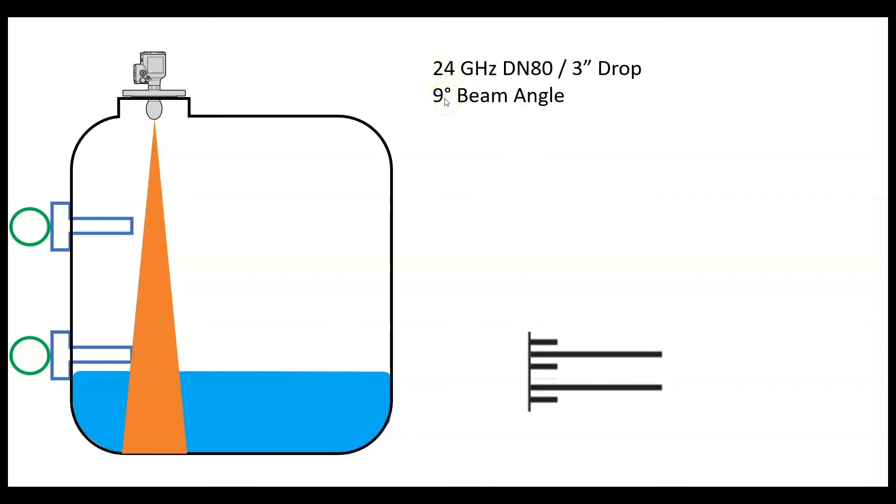You've got a 3-inch drop antenna on this one, a 9-degree beam angle. And the same size tank, same dimensions - it's going to miss the thermal well completely, doesn't touch it. Same thing here at the bottom. This is just an example, but it's going to say I see a level here, there's a thermal well.